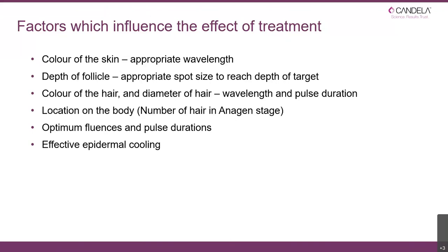The colour and diameter of the hair are also important, where wavelength and pulse duration are key considerations. Location on the body matters particularly because of the percentage of anagen hair in a specific area — the higher the percentage of anagen hair, the more hair you will destroy in each treatment, and also the speed of regrowth is higher. Using optimum fluences and pulse duration is important, and depending on the system, having an effective way of cooling the epidermis makes the treatment safer and reduces side effects.